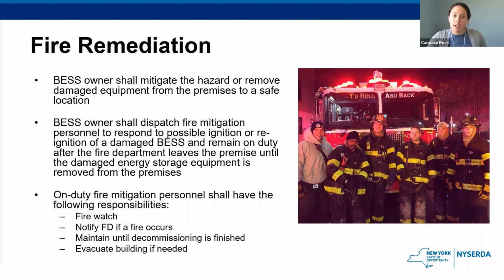All right, so here we have the fire remediation requirement. Where a fire or another event has damaged the energy storage system, the energy storage system owner shall, at their expense, immediately dispatch one or more fire mitigation personnel to the premises and remain on duty continuously after the fire department leaves and until the damaged system is removed, or earlier if the public safety hazard has been abated. So this requirement was put in place to alleviate the local fire service of potentially babysitting a storage system if there's been some sort of fire or event. There is a possibility that a storage system may reignite after extinguishment, so the owner should be responsible for the safety of these systems. A fire remediation company will be called to the scene to relieve the fire department and start the decommissioning process. And once again, I'll highlight that this should be done at the expense of the system owner.